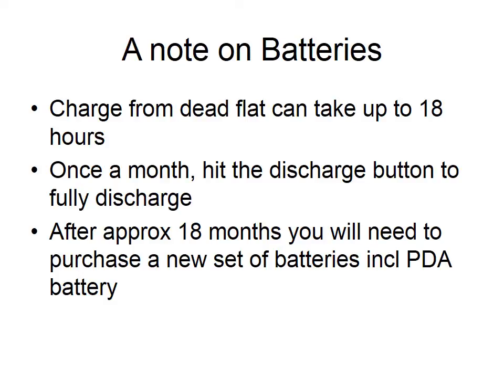A few notes on the batteries for the T3i unit. When the AA batteries are dead flat or close to, they can take 18 hours to become fully charged, so bear in mind the timing involved in keeping batteries charged. Once a month, or every couple of months at the outset, pop all your batteries into the charger and hit the little yellow discharge button. This will fully deplete every battery in the charger. Once all batteries are at 0%, they will fully charge up. That can take a full weekend, guys, so put it on Friday night and you'll be ready to go Monday morning.